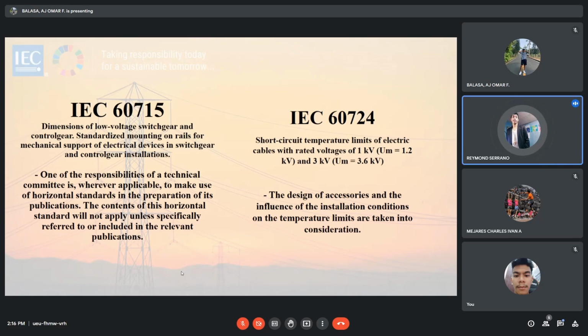That is, the 1 kV, then Um equals 1.2 kV and 3 kV, Um equals 3.6 kV, with regards to the following: insulation materials, oversheath and bedding materials, conductor and metallic sheath materials, and method of connections.